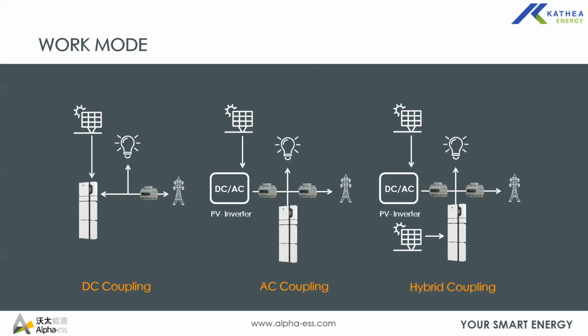And then if you have a scenario where you have to wire a PV array to the Alpha, and you have a PV inverter as well, that system is considered a hybrid. But all the meter wiring and configuration are the same as that of an AC coupling.